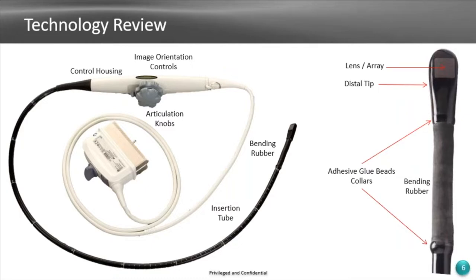And we have adhesive glue beads. This glue will break down even if you use the proper adhesive. There are very specific adhesives that we use that are compliant with the OEM recommended cleaners and disinfectants, but even those will break down over extended periods of time. And then the bending rubber here, which allows the head of the transducer to articulate.